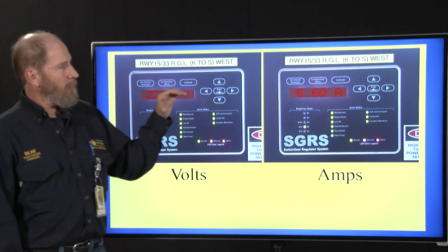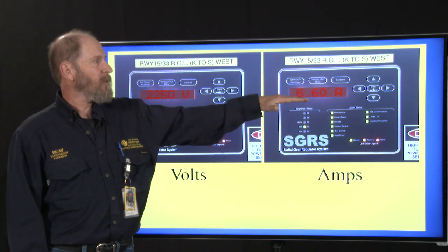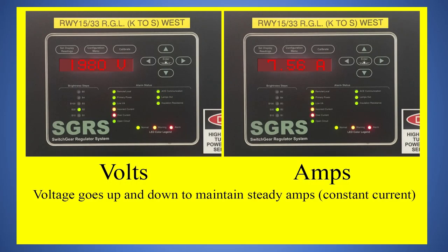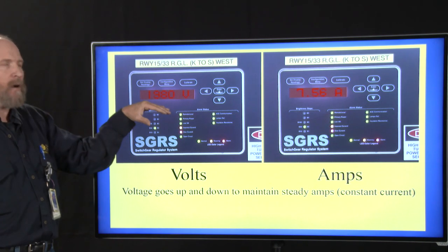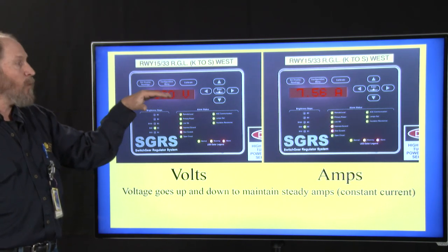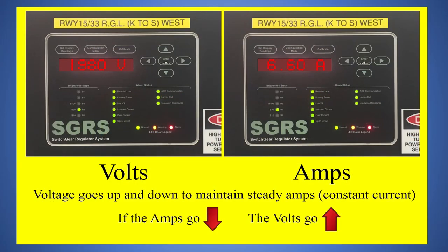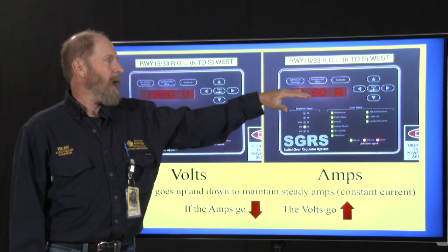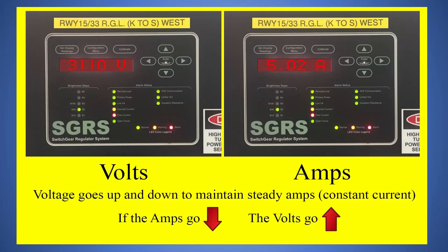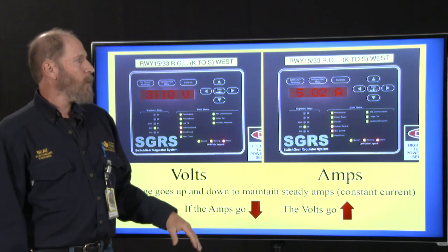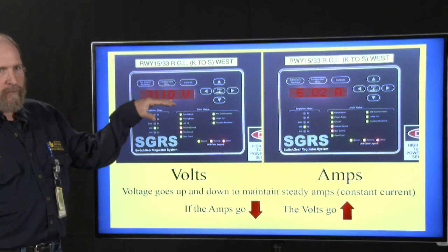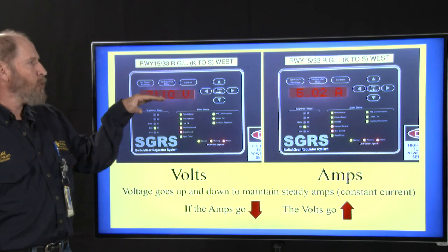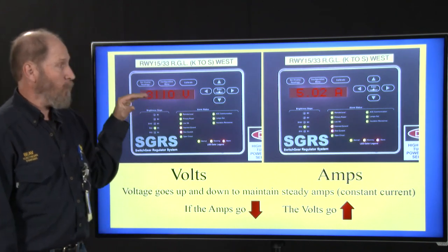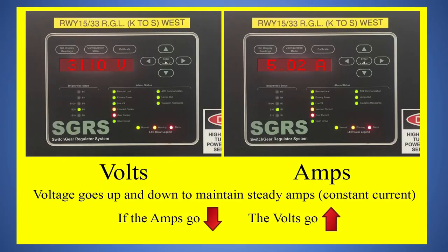So if we're trying to maintain this 6.6 amps or 6.6 gallons per minute, if this was to rise up higher than we wanted, what we would do is back off our pump and lower our pump pressure, or with an electrical system, we would lower our voltage. It would push fewer amps or less water, and it would bring it back to where we want. Okay, if it was to drop down low, we would increase our volts or increase our pump pressure, and we would push more amps or more electrons, or we would push more water in order to get our gallons per minute or our amperage back to where we want it.